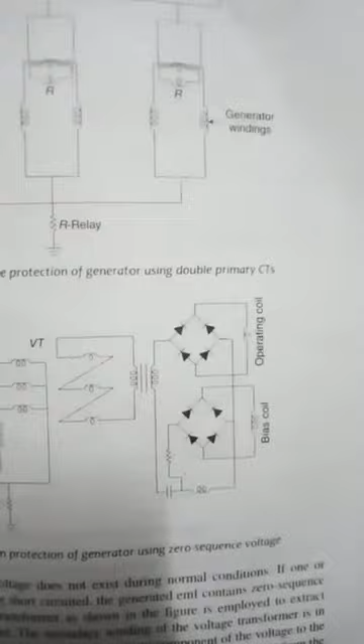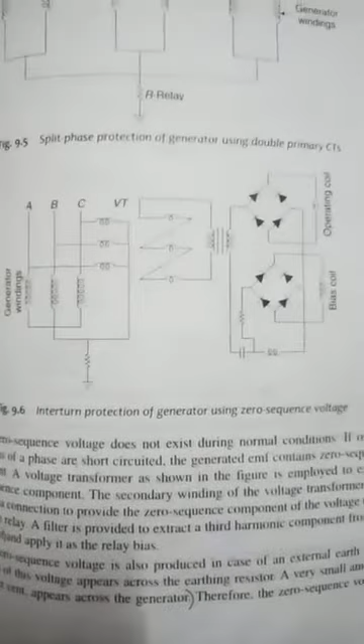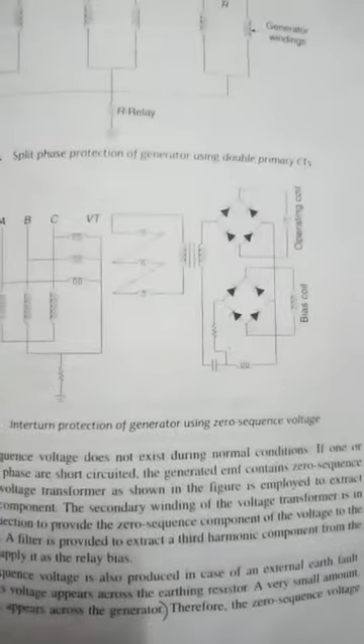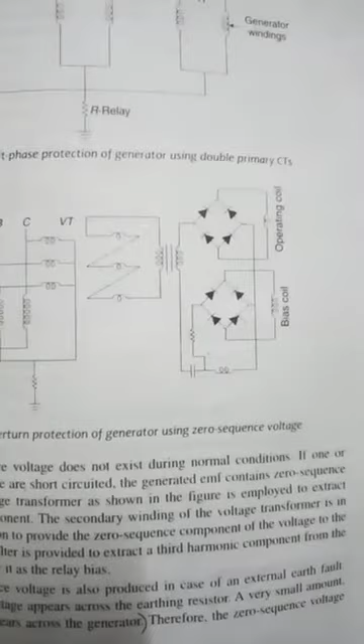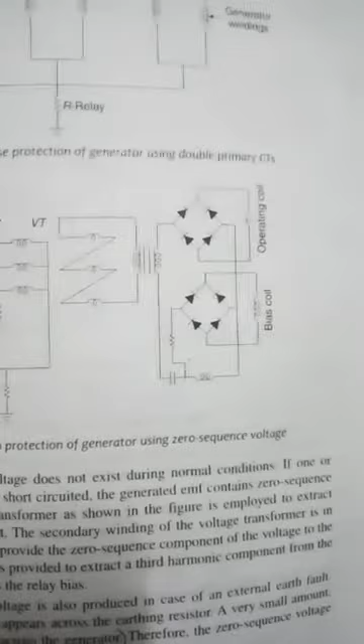So interturn protection based on zero sequence component is shown here in this figure. If generators do not have access to parallel windings, a method based on zero sequence voltage measurement can be employed for the protection against stator interturn faults. So this type of scheme will be applicable to single winding generators having multi-turn per phase per slot to protect against interturn faults.